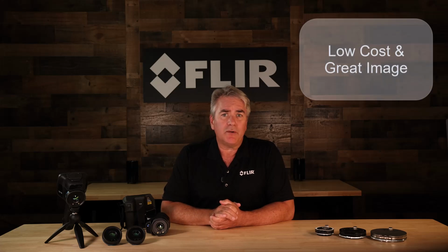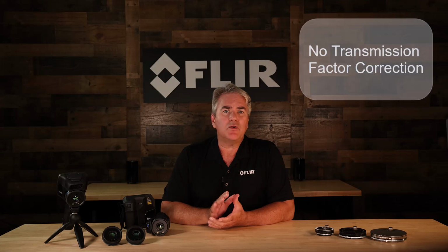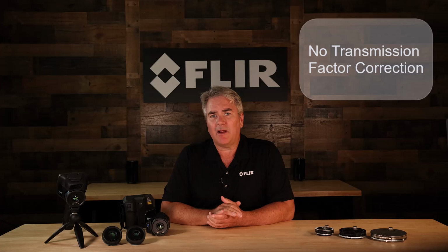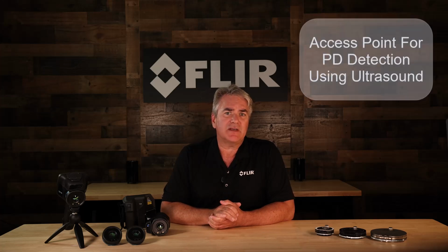There are several advantages to using the IRP1. The IRP1 is much lower in unit cost when compared to infrared windows, yet allows the wide field of view and great image that thermographers need. Second, there's no glass, so no transmission correction factor is needed to input into the camera, simplifying the inspection process. And third, the port can also be used as an access point for ultrasound detection of partial discharge within the cabinet. Let's have a look at how the IRP1 works with a lab setup.